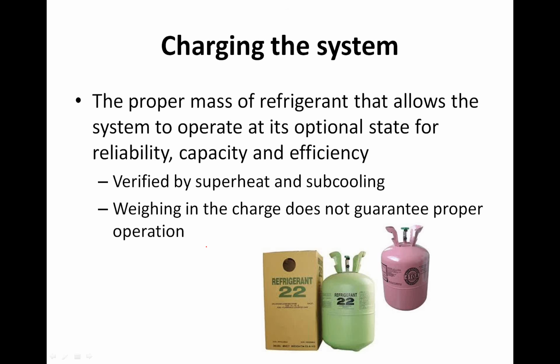And if you really want to think about it this way, you start with an empty system, and the manufacturer will add charge to the system, and as they add charge, the capacity increases, the amount of cooling goes up and up and up, till eventually it reaches the maximum amount of cooling that system is capable of doing. If we add any more charge to the system, then we're going to start to get a decrease in capacity because we're going to back refrigerant up in the condenser, or we're going to raise the evaporator pressure up if it's a fixed orifice device, and we're going to start to drop capacity off. So it's this perfect balance between the exact amount of refrigerant and the optimal cooling capacity. And once they figure that out, then they have a variety of methods that they charge the system. We're going to go over some of those now.